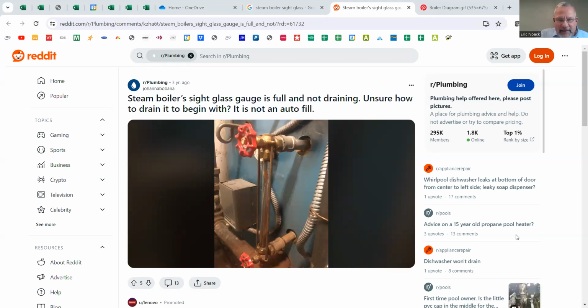So this is a sight glass, and this will be exclusively on steam boilers. It's going to be on the side, and as you can see, there's two pipes that come in and out at upper and lower levels, and then essentially a sight glass here that just fills up with water, and it indicates how full the boiler is. Steam boilers have to maintain a certain level of water in there, and essentially it's just boiling that water. The steam goes up and through the system, cools and condenses back into water, and then runs back to the system. So the way that they're piped has a really important part in this.